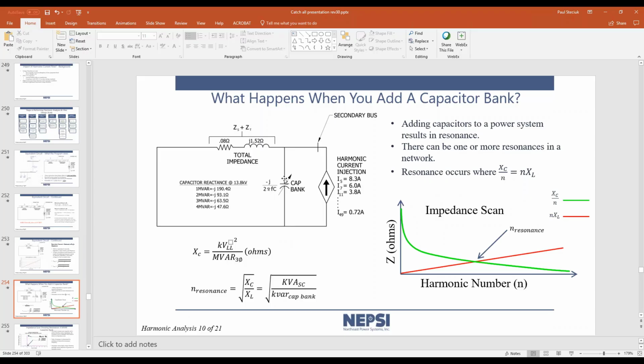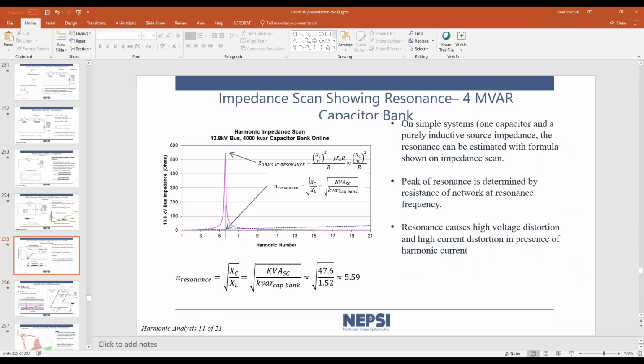When you add a capacitor, remember, its impedance varies as XC divided by N, XC being the capacitive reactance of the network. That capacitor's impedance curve looks like this, the green curve. As the harmonic number goes up, the impedance drops off. So you end up with two different types of responses to harmonic current between a capacitor and a reactor. When you have a system that includes both a capacitor and a reactor, you end up with a resonance. This is an impedance scan that actually shows a resonance. The pink curve represents the resonance. The x-axis is harmonic number, excuse me, and the y-axis is ohms.